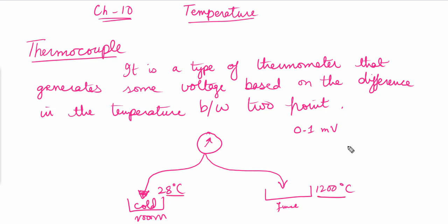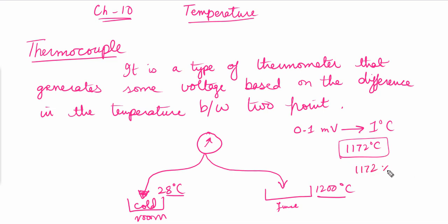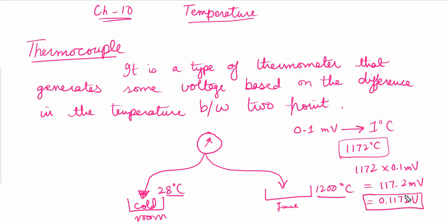With a difference of 1172°C and a scale of 0.1 millivolts per degree, the thermocouple will generate 1172 × 0.1 = 117.2 millivolts, or 0.1172 volts. This voltage is generated based on the temperature difference between the two ends of the thermocouple, making it suitable for measuring very high temperatures.